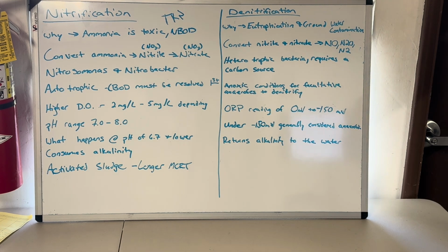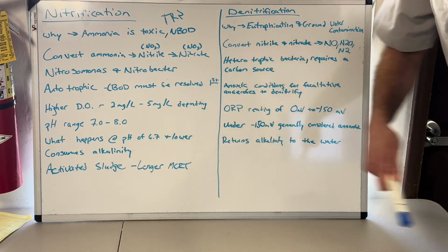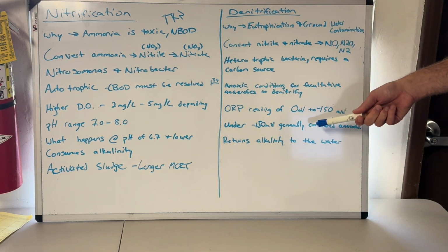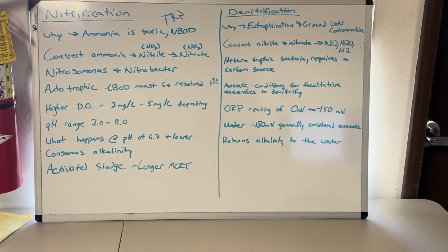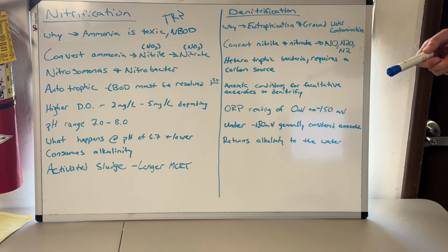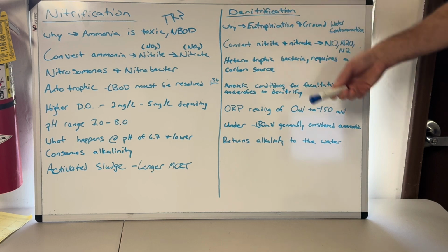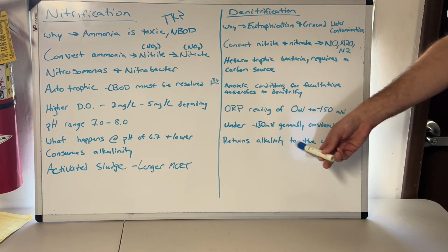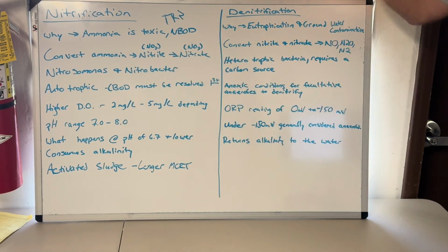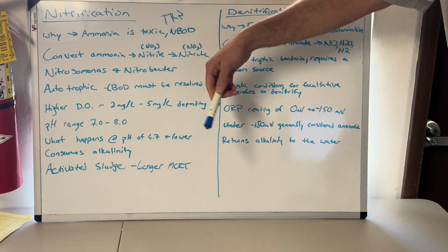Okay, in a healthy plant such as mine, I'm not being braggy about my wonderful plant, but it is healthy. And so let me show you how you don't have to fear alkalinity being consumed, because my influent is pretty alkaline. It's got a decent amount of alkalinity in it. It's going into that anoxic zone. My influent is coming into the anoxic zone. My return to that anoxic zone denitrifies, okay, and it releases more alkalinity into the water. Sorry, into the mixed liquor.